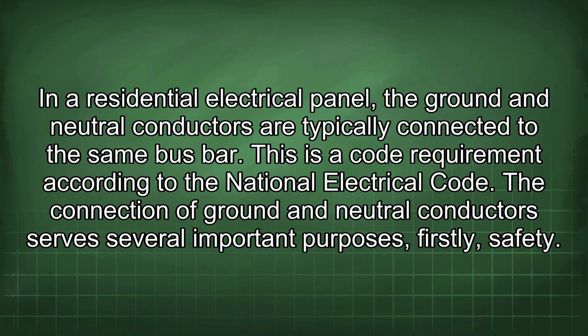In a residential electrical panel, the ground and neutral conductors are typically connected to the same bus bar. This is a code requirement according to the National Electrical Code. The connection of ground and neutral conductors serves several important purposes.